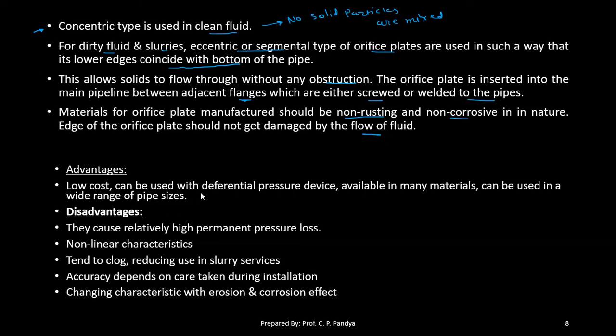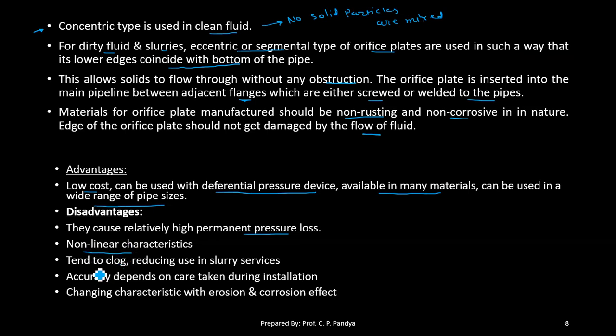Advantages of the orifice plate: low cost, can be used with differential pressure devices, available in many materials, and suitable for a wide range of pipe sizes. Disadvantages: it causes relatively high pressure loss, possesses non-linear pressure-flow measurement characteristics, tends to clog with slurry particles, its accuracy depends on the care taken during installation, and changing characteristics due to erosion and corrosion affect performance.